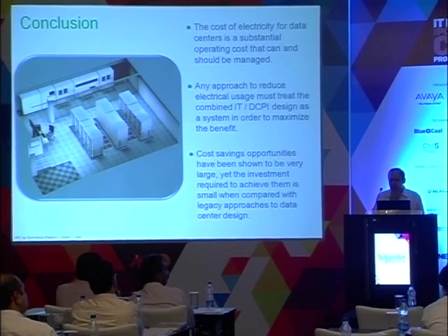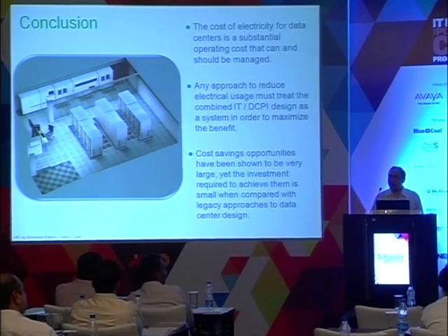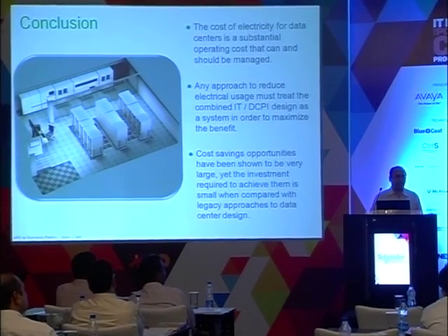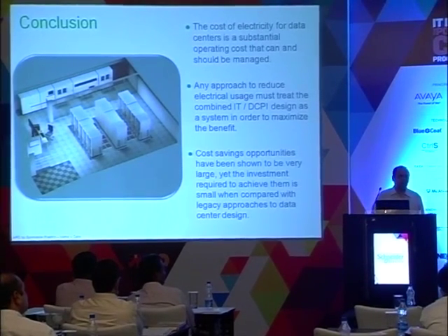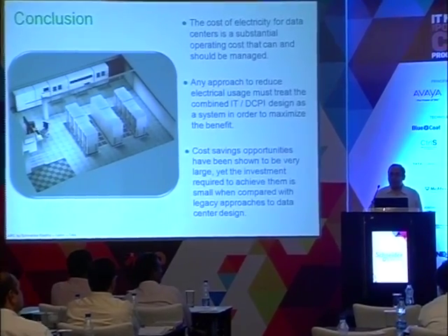The third is cost saving opportunities are very large. We are talking about data centers in India where the PUE is much beyond 3. The reason people are not scared about it is because they don't know. Sometimes when we do an audit for a data center, we suddenly wonder whether we have calculated something wrong because the PUE is coming to 3.6, right? And that is when everybody gets woken up that, hey, there's a lot that can be done.